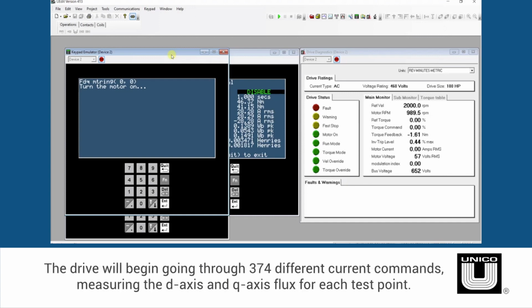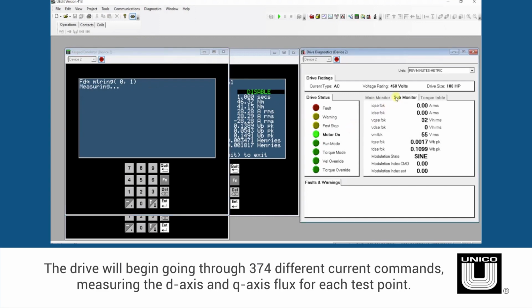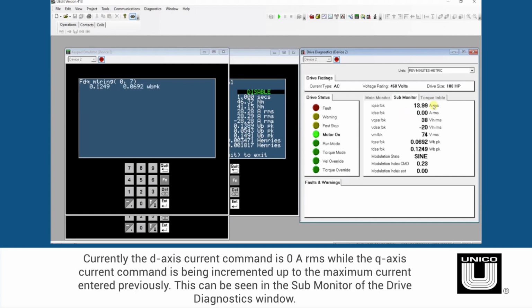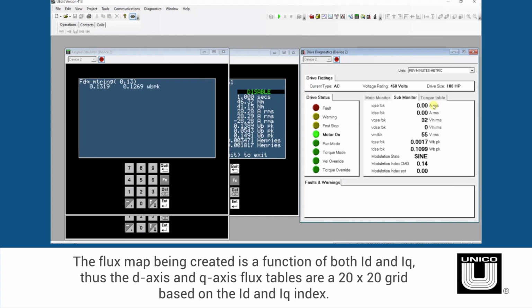The drive will begin going through 374 different current commands, measuring the D-axis and Q-axis flux for each test point. Currently, the D-axis current command is 0, while the Q-axis current command is being incremented up to the maximum current entered previously. This can be seen in the sub-monitor of the drive diagnostics window. The flux map being created is a function of both ID and IQ. Thus, the D-axis and Q-axis flux tables are a 20 by 20 grid based on the ID and IQ index.